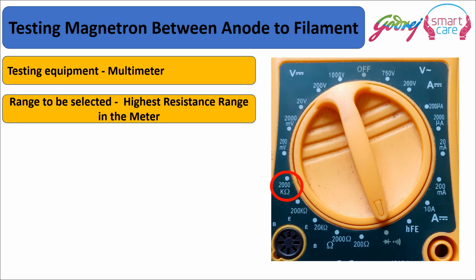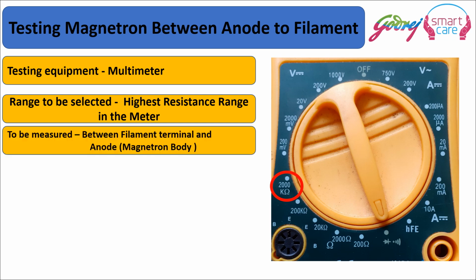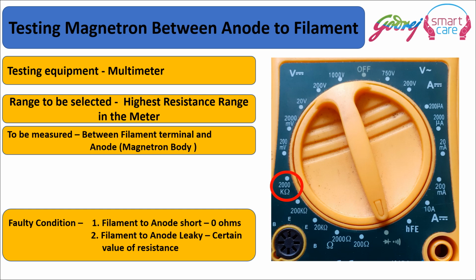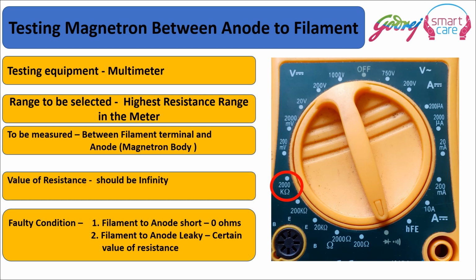Again, testing the magnetron between the anode and the filament, set the multimeter to the highest range of resistance, and then measure between the filament terminal and the anode of the magnetron body, that is, the magnetron body and the filament terminal. Filament to anode, if it is short, if it is body short, then it will give 0 ohms. If it is leaky, it will give a certain value of resistance. Ideally, the value should be infinity.